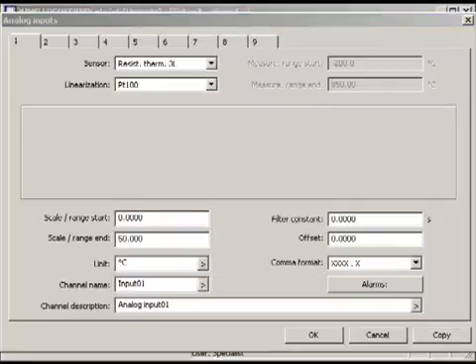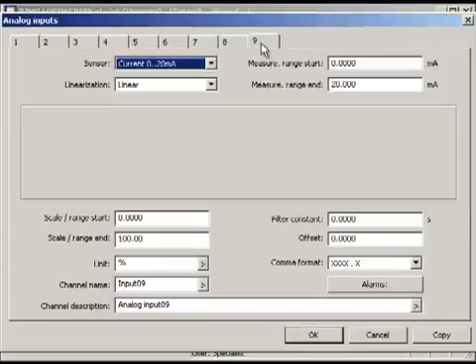The humidity sensor is connected to analog input 9, with 4 to 20 mA signal, which corresponds to 0 to 100% relative humidity.